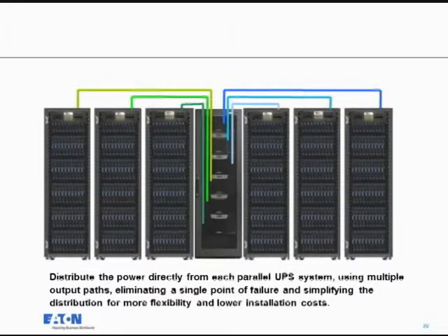So really, you have a power system made up of multiple UPSs. Deploy a multiple distribution path, a multiple distribution system along with it. Now, I also get the floor space, the physical space, by not requiring the extra distribution and the extra panels. So why do you want to go modular? Well, it's a pay-as-you-grow, right? I gain the reliability, gain the performance, but I don't have to pay for that oversizing or those fudge factors.